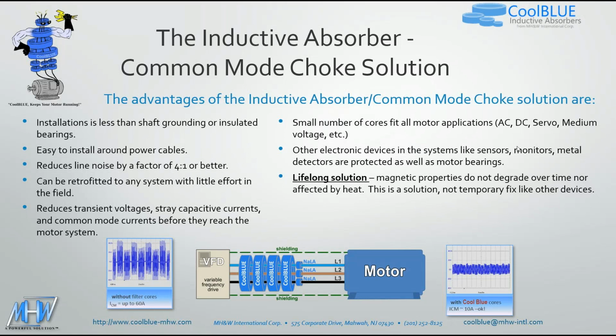The advantages of this solution. Installation is less than shaft grounding or insulated bearings. It's easy to install around the power cables. We can reduce the line noise by a factor of 4 to 1 or better. It can be retrofitted to any system with little effort in the field. We reduce the transient voltages, stray capacitive currents, and common mode currents before they reach the motor system. So we're nipping it in the bud right at the VFD. A small number of cores fit all motor applications, AC, DC, servo, etc. Other electronic devices in the system like sensors, monitors, metal detectors are protected as well as motors. This is a key thing which none of the other solutions do.